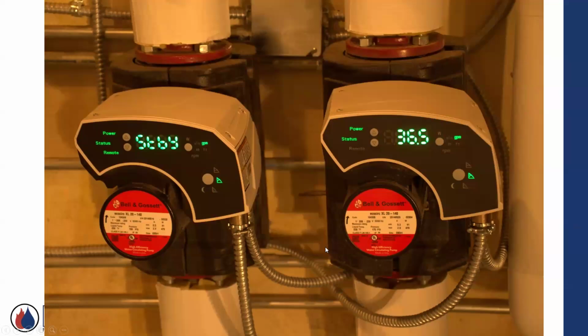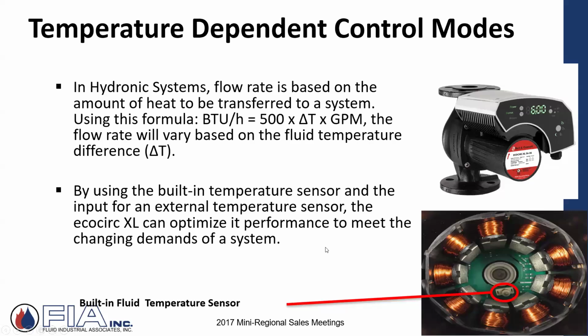Just some examples out in the field. The contractors, the pipe fitters, when they put this stuff in, they like this type of feedback. There are digital displays on these pumps, so they let the contractor or troubleshooter, or if we're out there in the field helping set up or troubleshoot, we see what's going on. We've got flow rate, feet of head, and RPMs. So there's a little bit of information going on.